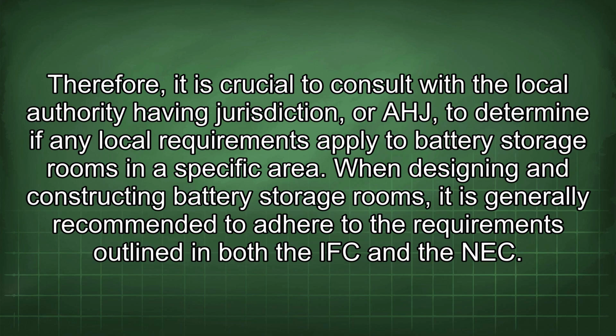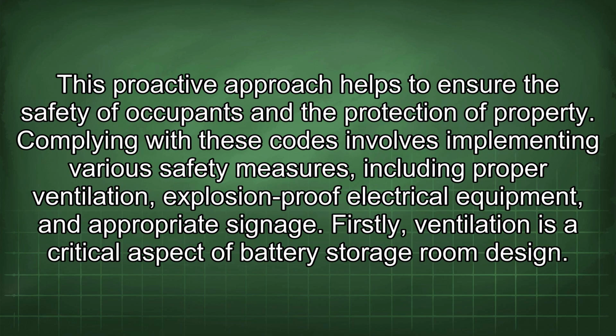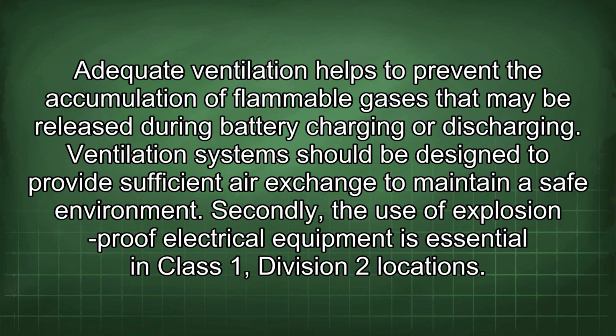When designing and constructing battery storage rooms, it is generally recommended to adhere to the requirements outlined in both the IFC and the NEC. This proactive approach helps to ensure the safety of occupants and the protection of property. Complying with these codes involves implementing various safety measures, including proper ventilation, explosion-proof electrical equipment, and appropriate signage. Firstly, ventilation is a critical aspect of battery storage room design. Adequate ventilation helps to prevent the accumulation of flammable gases that may be released during battery charging or discharging. Ventilation systems should be designed to provide sufficient air exchange to maintain a safe environment.